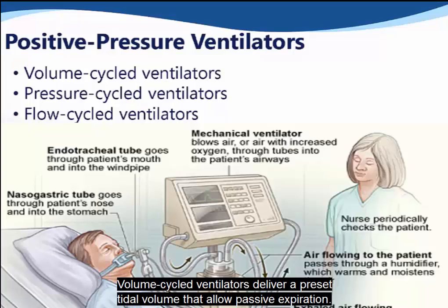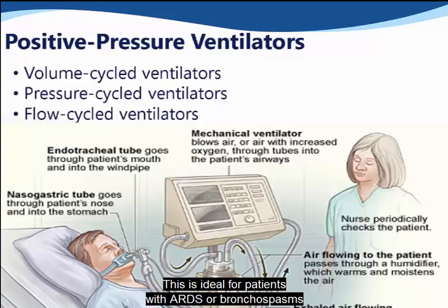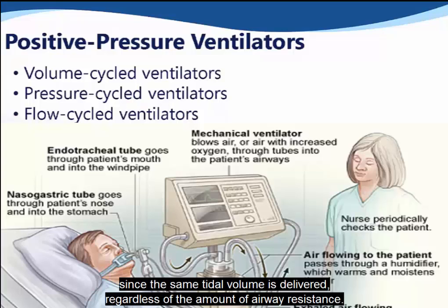Volume cycle ventilators deliver a preset tidal volume and allow passive expiration. This is ideal for patients with ARDS or bronchospasms, since the same tidal volume is delivered regardless of the amount of airway resistance. This type of ventilator is the most commonly used in critical care environments.